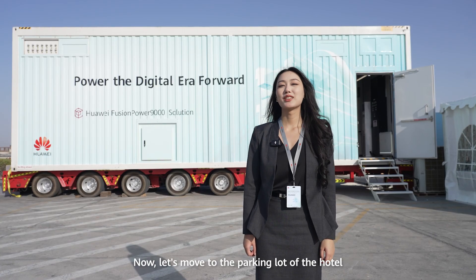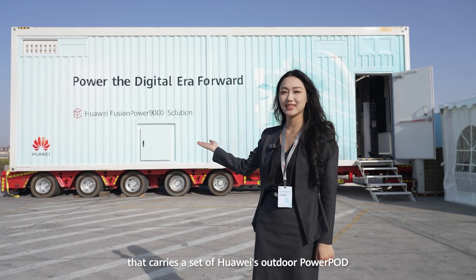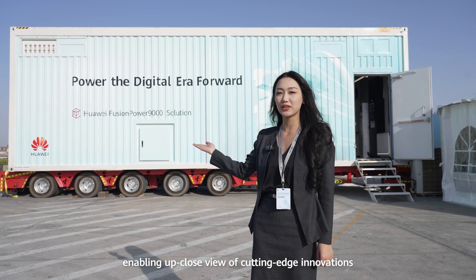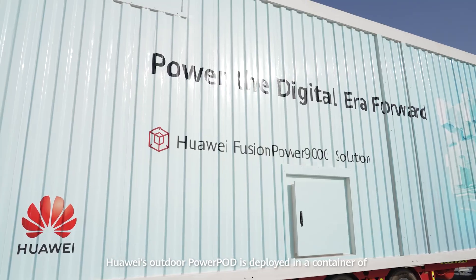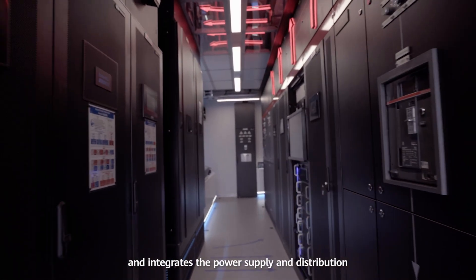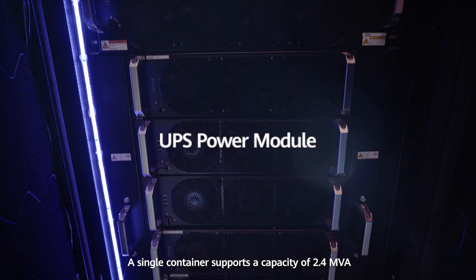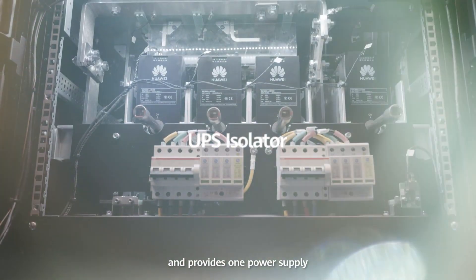Now, let's move into the parking lot of the hotel. Here we can see a demo truck that carries a set of Huawei Outdoor PowerPOD, enabling a close view of its innovations. Huawei's Outdoor PowerPOD is deployed in a 40-foot container with ultra-high protection performance, integrating power supply and distribution, UPS, and lithium battery systems. A single container supports a capacity of 2.4 megawatts and provides one power supply per row.